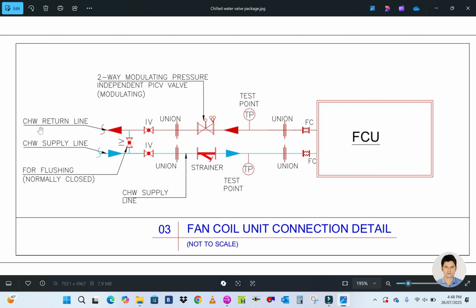In the same way, in the return line, you can see there should be one isolation valve here, and next will be the control valve, which may be a two-way valve or a three-way valve, depending on the design. Here they are using a two-way modulating pressure independent control valve. Modulating type is two-way. Two-way is nothing but variable flow. So wherever there is variable flow, you can use the two-way valve, because the water coming from the chiller goes to the FCU and returns through this return line to the chiller. So the two-way valve is called a variable flow valve.